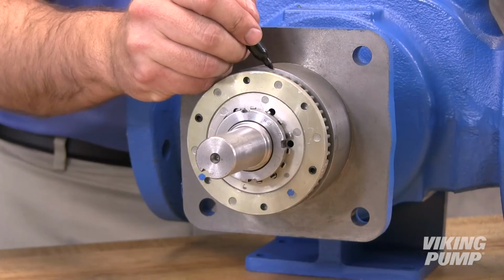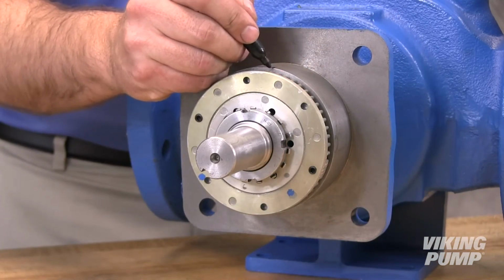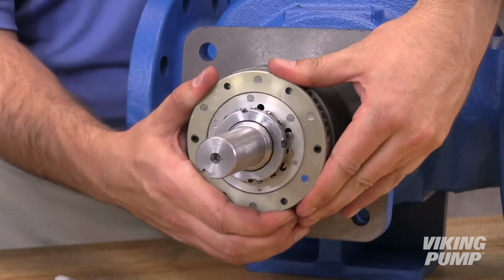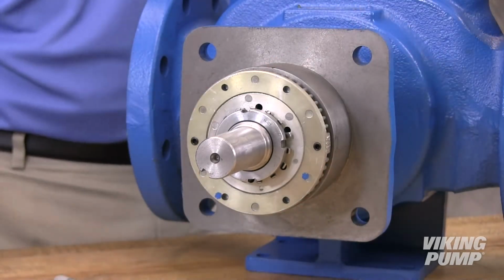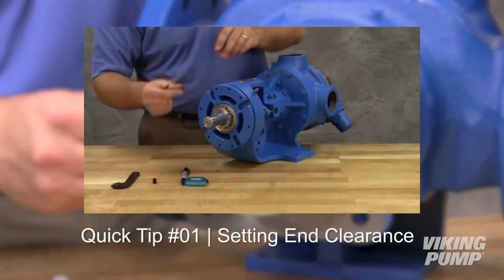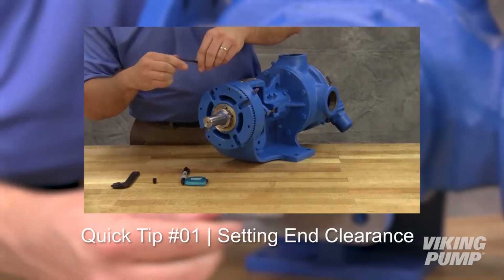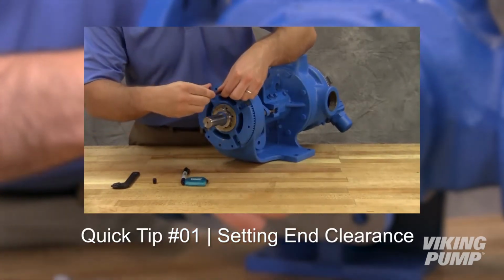Mark the position of the bearing housing with respect to the casing. You are now ready to set the end clearance and lock in place with the bearing housing set screws. For information on this step, please refer to our video, Setting End Clearance.